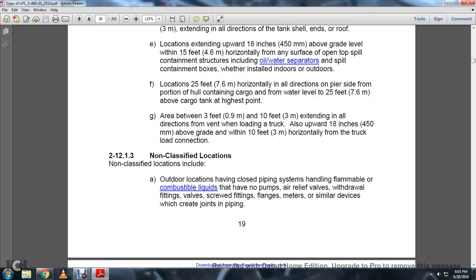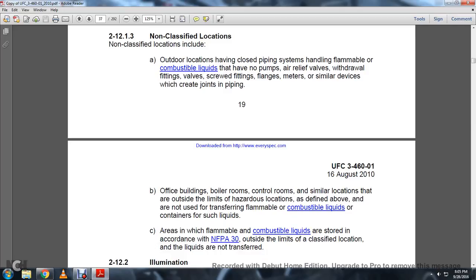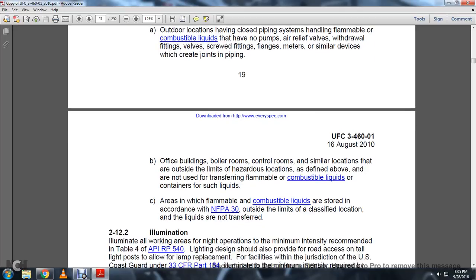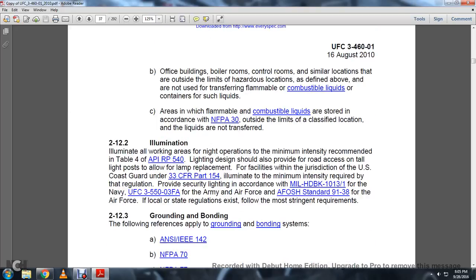2-12.1.3 Non-classified locations. Non-classified locations include outdoor locations having closed piping systems for flammable or combustible liquids with no pumps, air relief valves, withdrawal fittings, valves, screw fittings, flanges, meters, or similar devices which create joints in the piping; office buildings, boiler rooms, control rooms, and similar locations that are outside the limits of the hazard location as defined above; areas not used for transferring flammable or combustible liquids; and areas where flammable or combustible liquids are stored in accordance with NFPA 30 outside the limits of a classified location, or where liquids are not transferred.